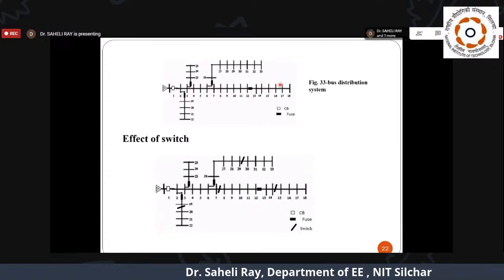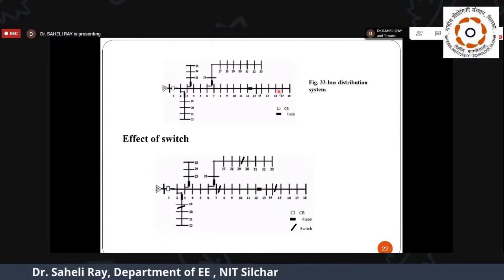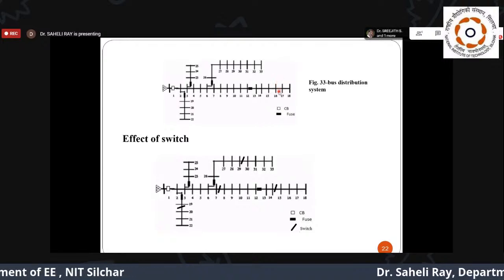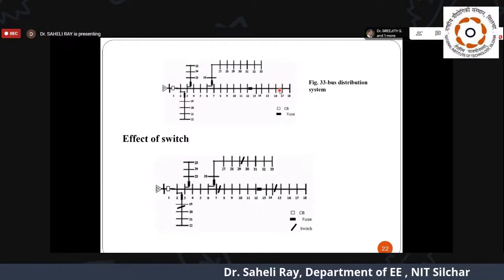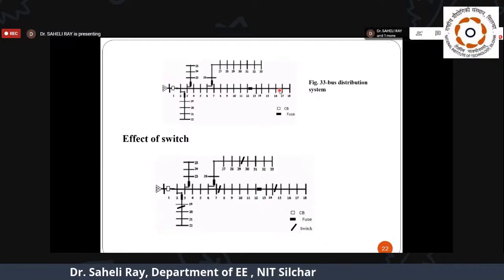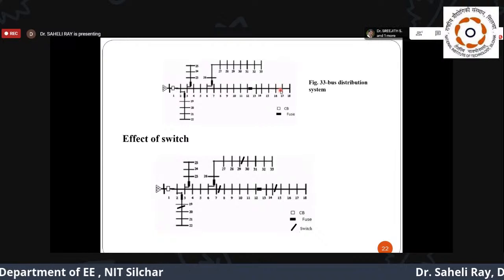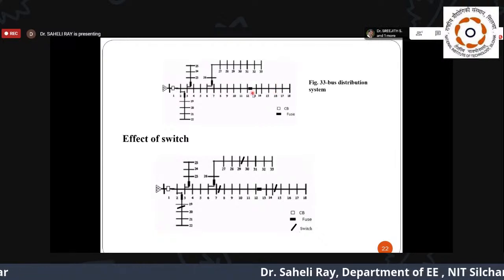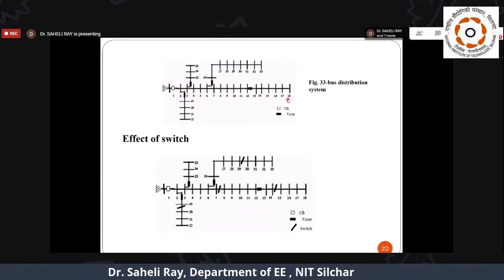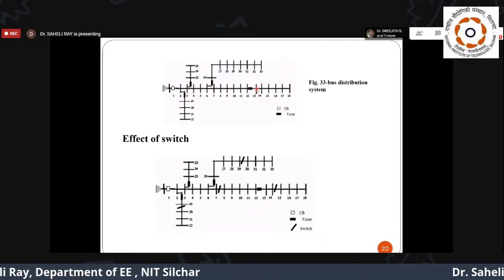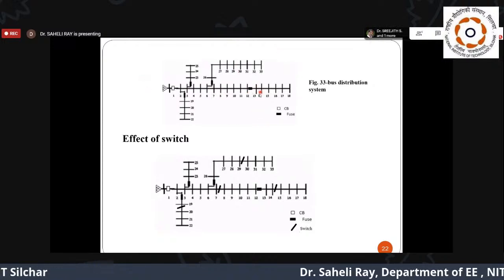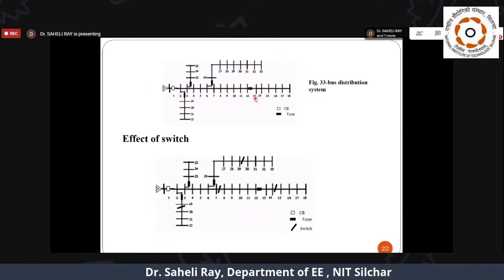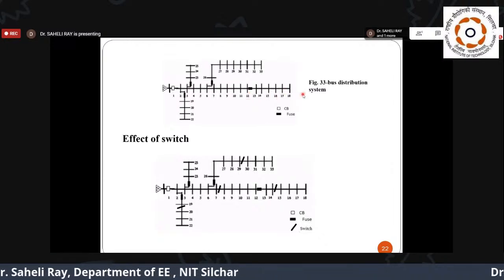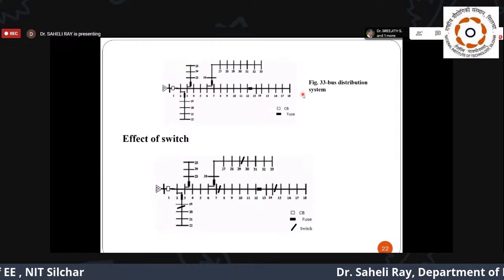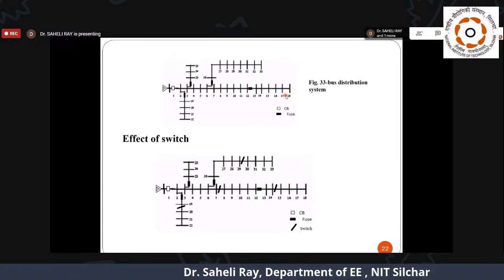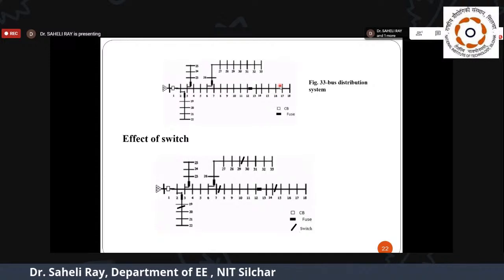Suppose a fault occurs between load point 16 and 17. What will happen then? All the load points starting from 13, 14, 15, 16, 17, 18 will be affected, because this fuse will operate and isolate this portion from the remaining system. Each of these load points 13 through 18 will be affected since they are connected together, and power will be restored only after the fault is repaired.